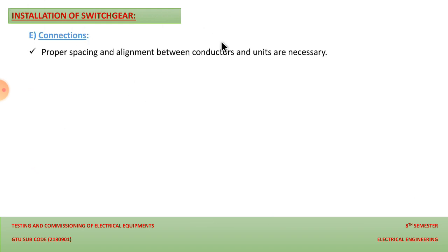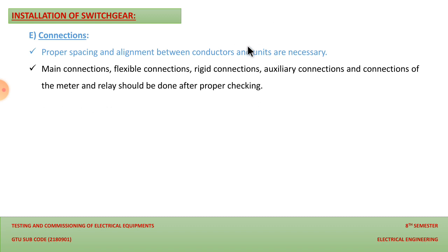Then the next point that we should keep in mind while we are installing the switchgear is connections. So yes, proper spacing and alignment between conductors and units are necessary, so that it will be more convenient while we are performing operation and maintenance in future. So one can easily see the layout and the path of the wiring. And the main connection, flexible connection, rigid connection and auxiliary connections, and the connection of the meter and the relay should be done after proper checking. So this is a part of the wiring layout, and we should keep in mind these points while we are making a connection of the switchgear.